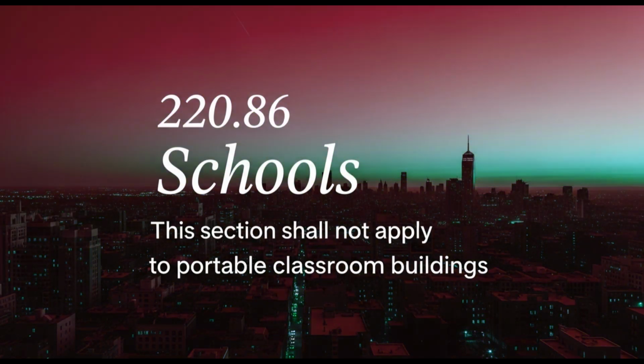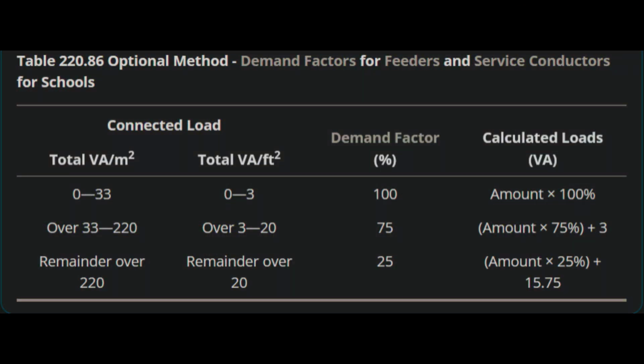Okay, so bringing it all together, the so what for the industry. You use this optional calculation, you apply these demand factors, maybe size down the neutral. What's the big impact? The big impact comes from a crucial efficiency clause related to the overall service size. The NEC states that the ampacity of any individual feeder within the building doesn't need to be larger than the total ampacity calculated for the entire building using this optional method. Ah, okay, so the whole building calculation sets the ceiling. Exactly, and that ceiling is often much lower with Section 220.86.